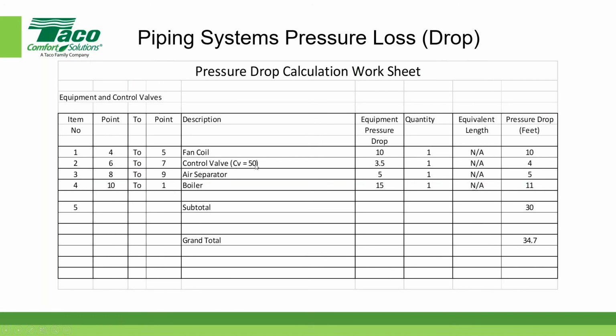So when I look at my little table here, my control valve has a CV equal to 50, but the flow is 61.5. So if you recall the equation I used before, I took the ratio of the flows, in this case 61.5 divided by 50, and that ratio comes out to 1.23, and I square that times the initial pressure drop of 1. My new pressure drop is 1.5 pounds per square inch. I have to multiply that by 2.31 to convert it from pounds per square inch to feet, which comes out to roughly 3.5 feet, and I rounded it off to 4 feet. Any questions about how I calculated the pressure drop for the control valve? Nope. I think everybody sees that.